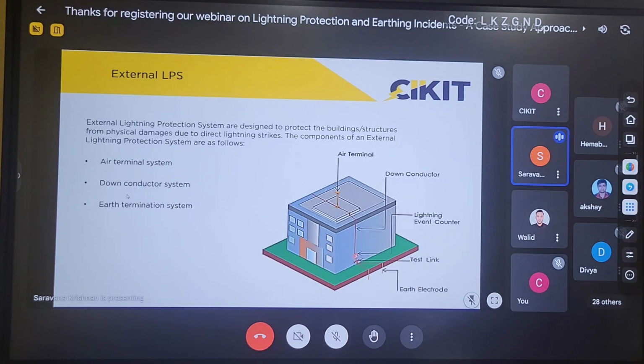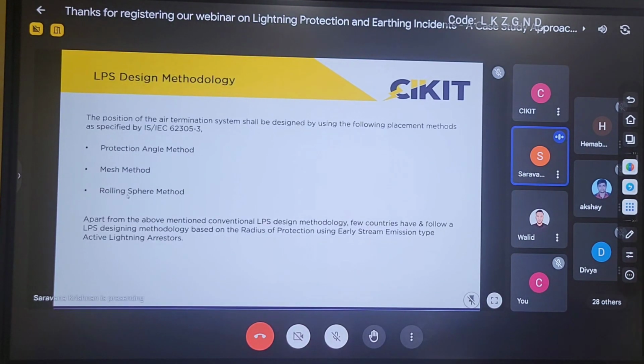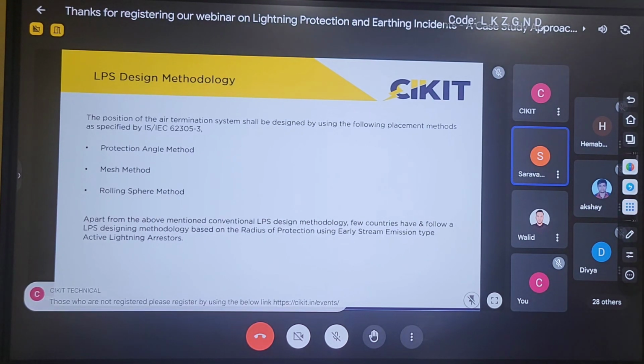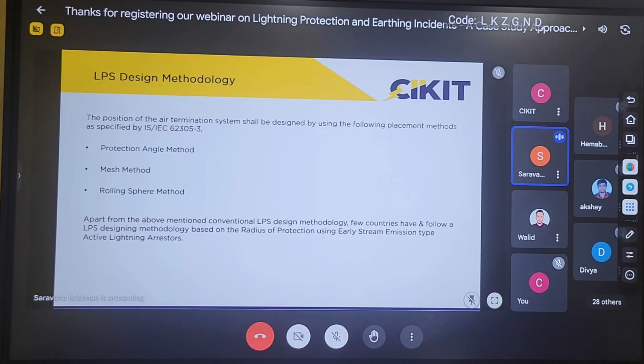We have to perform designing for all these three components, and most importantly, the first component, air termination system designing, mainly depends upon the level of protection. The standard has explained three different methodologies for performing this designing of the lightning protection system. These three methodologies are called air termination placement methodologies, which means how to determine the position of air terminals.